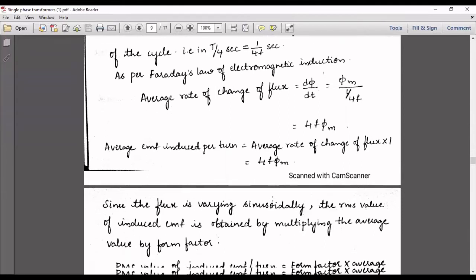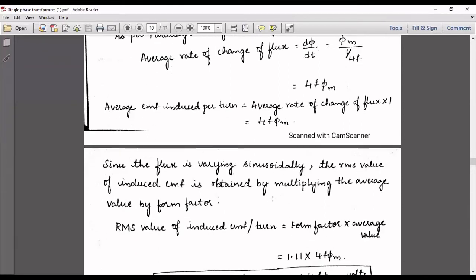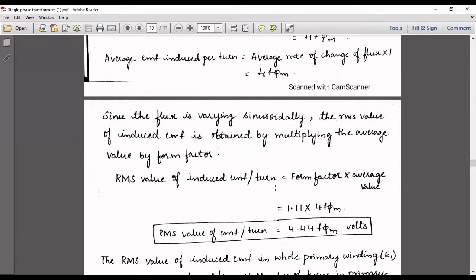Since the flux is varying sinusoidally, the RMS value of induced EMF is obtained by multiplying the average value by the form factor. We know that the RMS value of any alternating quantity is given by form factor into average value. Form factor is a constant value, the ratio of RMS to average value. Therefore, it is 1.11 into 4 f phi maximum. The RMS value of EMF per turn will be 4.44 f phi maximum volts.